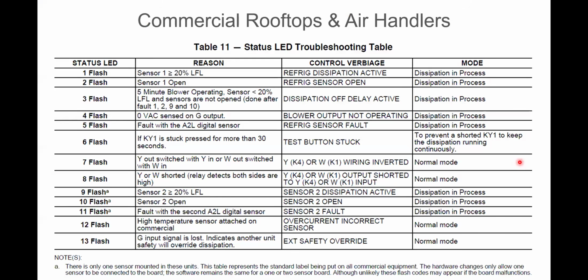Those kind of things. If it's a bigger rooftop unit, it may have a board in it that can handle 2 sensors, in which case I will inherit 1, 2, 3, 4, 5 more flash codes for the second sensor on the board. And there's even a few rooftops that could have as many as 3 on there.